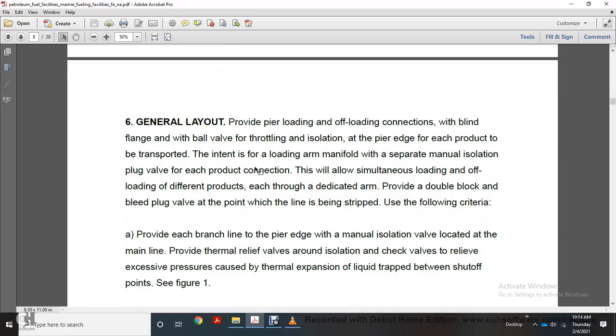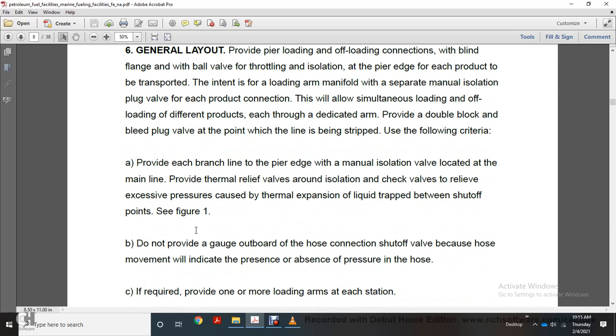6. General layout. Provide a pier loading and offloading connection with a blind flange, ball valve, and throttle isolating valve at the pier edge for each of the products to be transported. The intent is that the loading arm manifold will be separated with a manual isolation plug valve for each product connection. This will allow simultaneous loading and offloading of different products, each with a dedicated arm. Provide a double block and bleed plug at the point at which the line is being stripped, using the following criteria. Provide each branch with a pier edge manual isolation valve located at the main line. Provide thermal relief valves around the isolation check valve to relieve excessive pressure caused by thermal expansion of liquid trapped between shutoff points. See Figure 1.